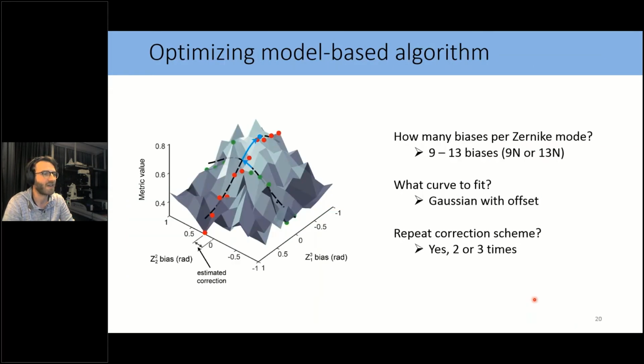So fairly quickly, model-based optimization: you take a sequence of biases which you apply for a certain Zernike mode, and then you calculate the metric value, and then you fit a curve through this. It's called the metric curve. Then you find the optimum, and then you go on to the next Zernike mode. This is sometimes called a 3N correction scheme, but it depends on how many biases you take. We did a lot of optimization for this, and we found that we need to take about 9 up to 13 biases per Zernike mode to get reliable correction. So it's a 9N or a 13N correction. Secondly, a Gaussian with an offset corresponds quite well with the metric curve. And we found that we need to repeat the correction scheme multiple times to improve the correction.